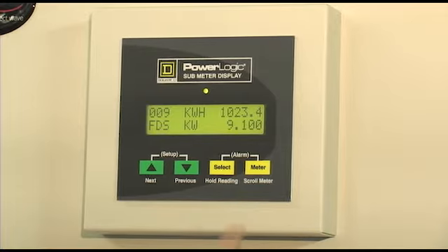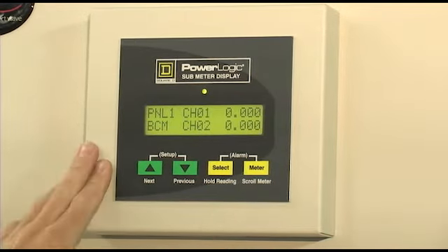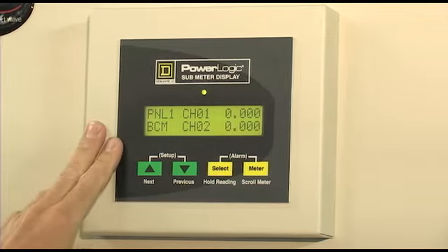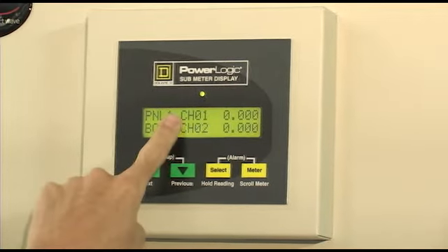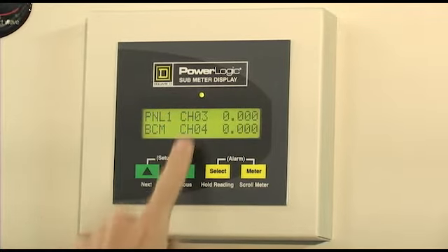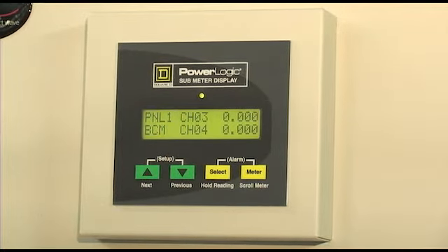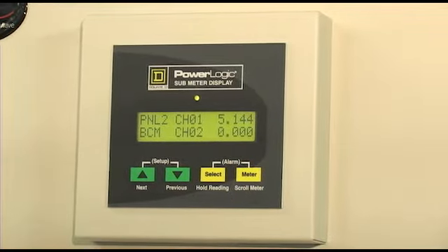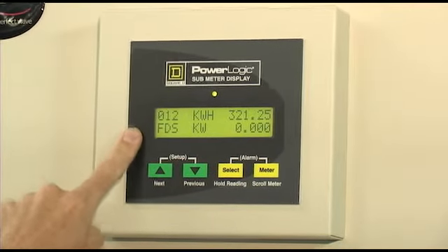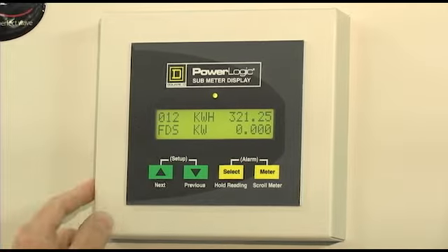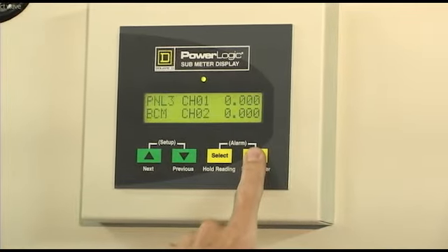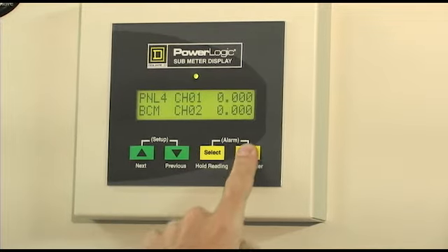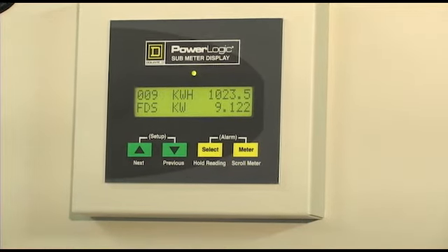You can press the meter button here, and what it'll do is it scrolls through panel 1, which you can scroll individually. This is channel 1 indicating circuit 1, circuit 2, circuit 3 and 4 up to 42. You press the meter button, it'll go to panel board 2, probably the one down here. Yep. And you can scroll and look at various circuits to see what the amperages on those are. The third actuation is the kilowatt hours and the kilowatts of the panel boards 1 and 2. And then as you scroll through, you'll have panel board 3, panel board 4, and then the totals for panel board 3 and 4. That's basically what you have for there.